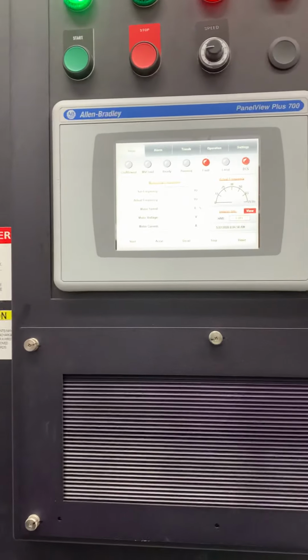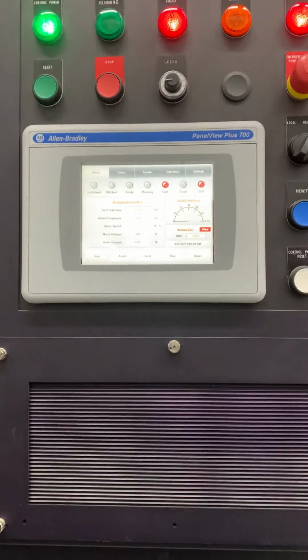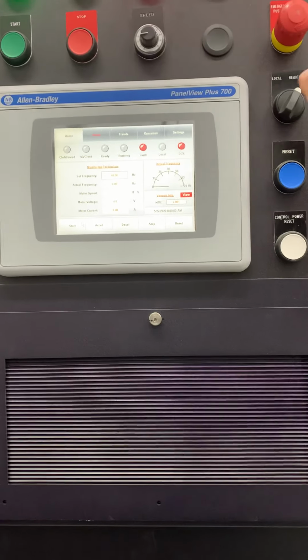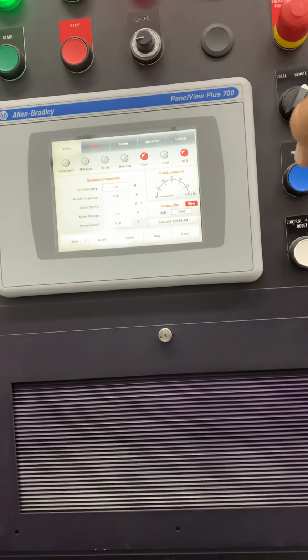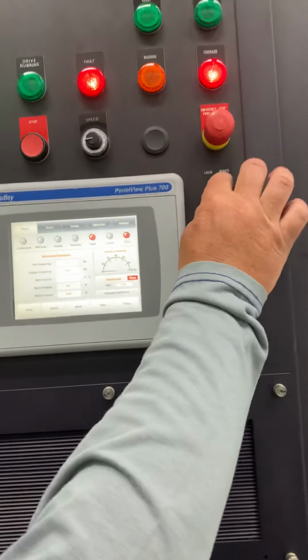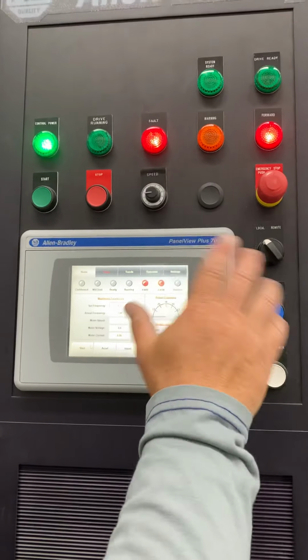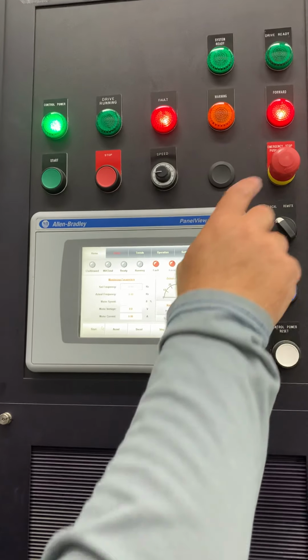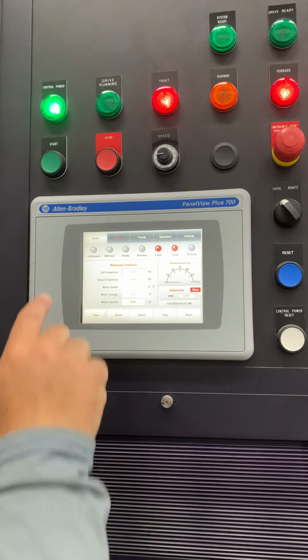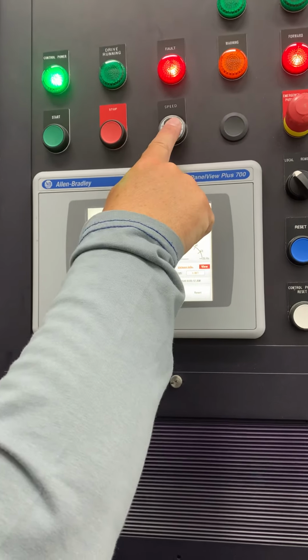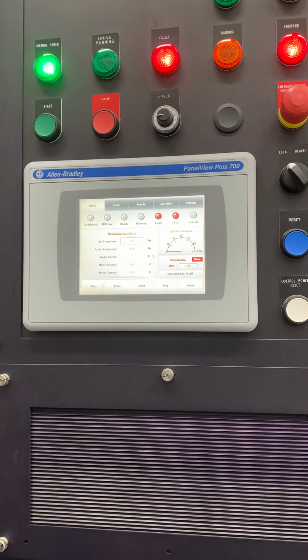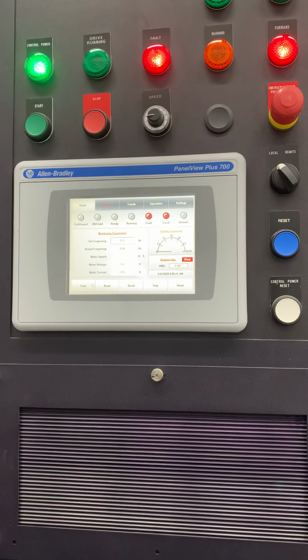This control right here should always be in remote if it's talking to the system, but to run the drive locally, it's as simple as going to local, and here's where you adjust your speed. So you just switch it over to local, and as soon as you do that, you still have to actuate the e-stop. But then you can use the start, stop, and the speed control here locally. That's simple.